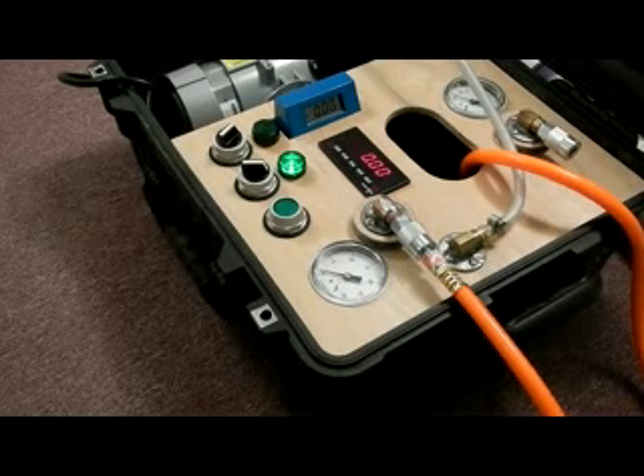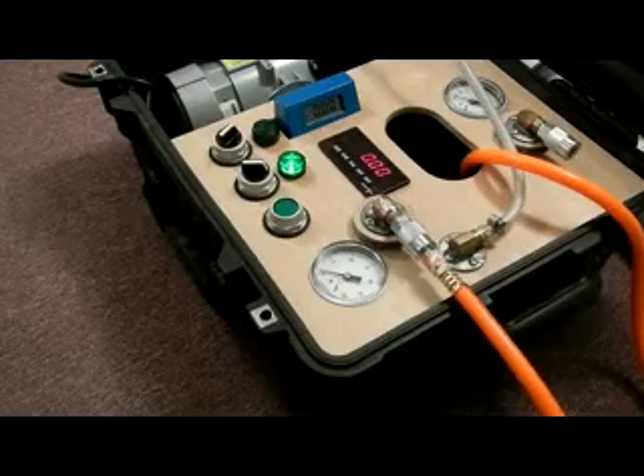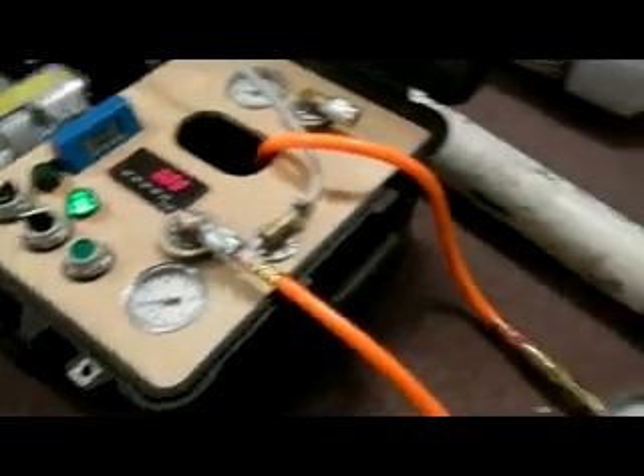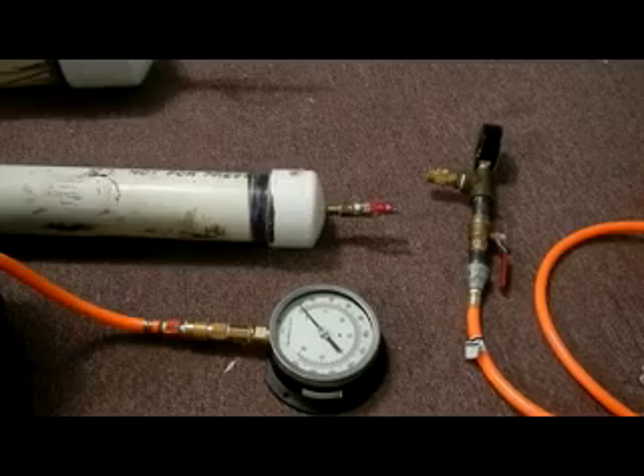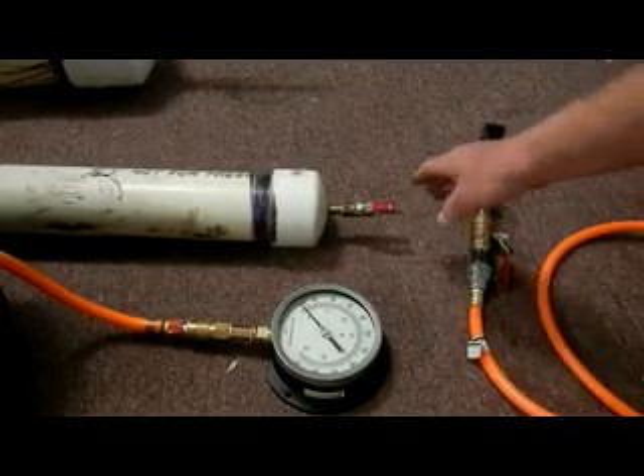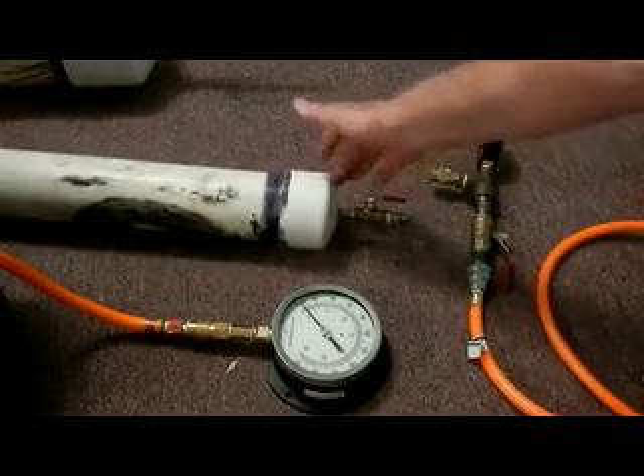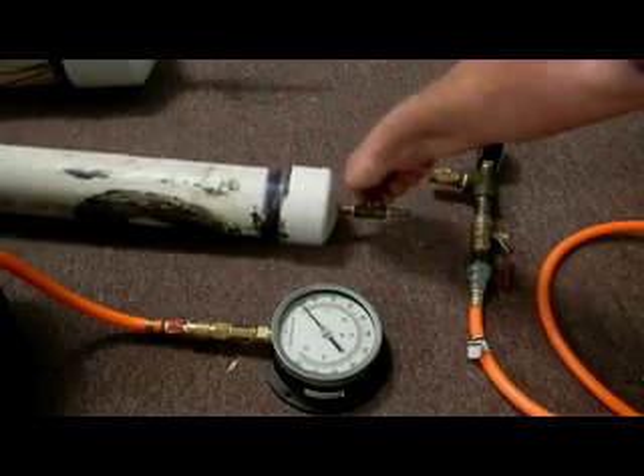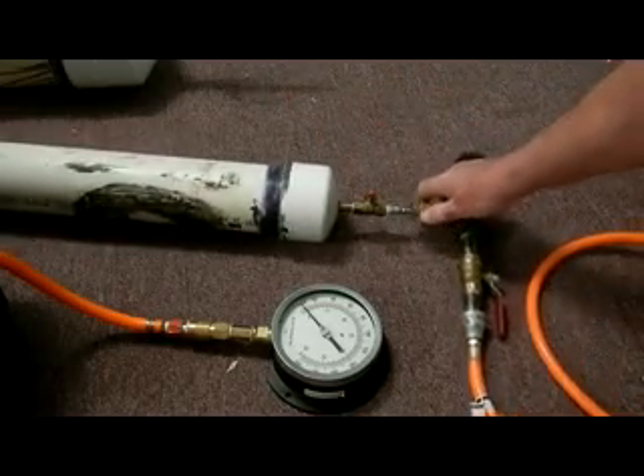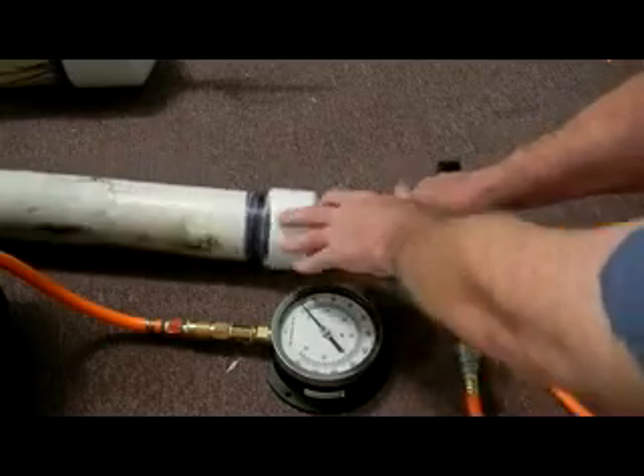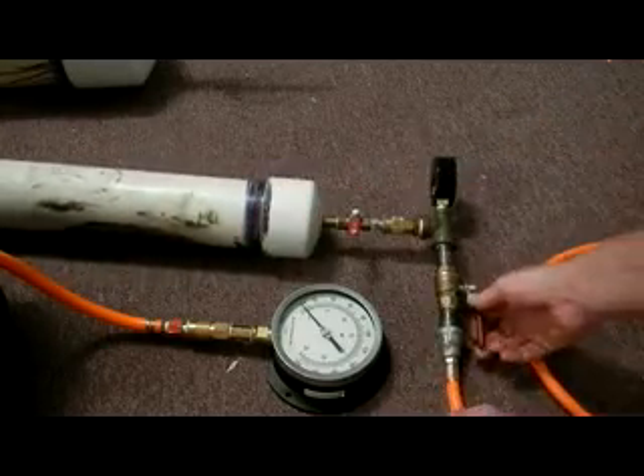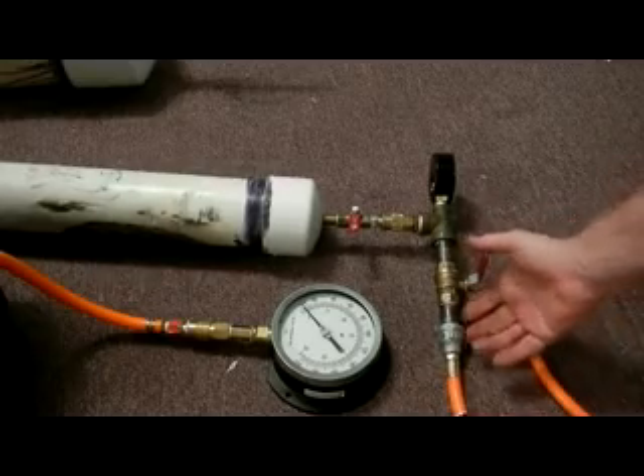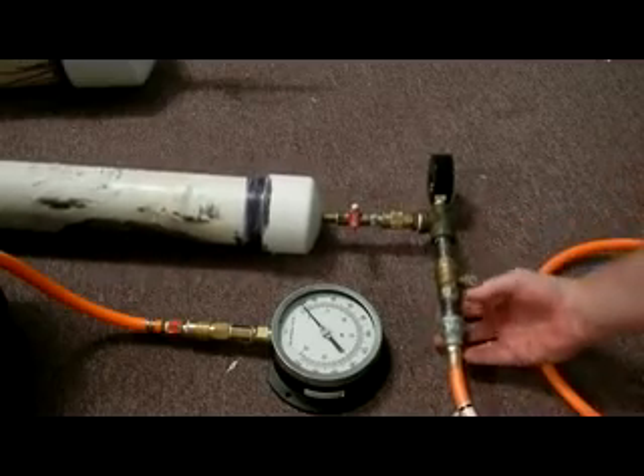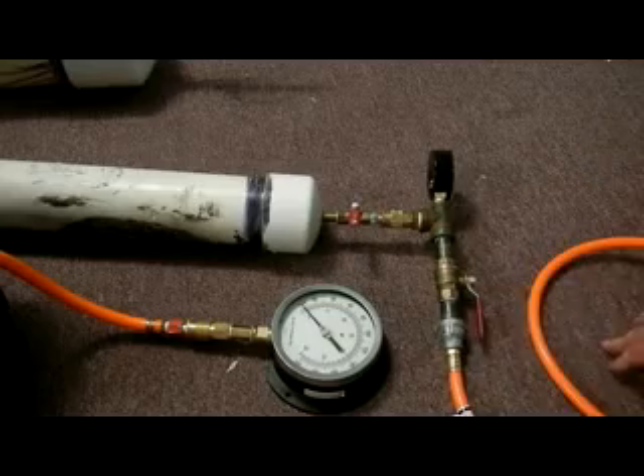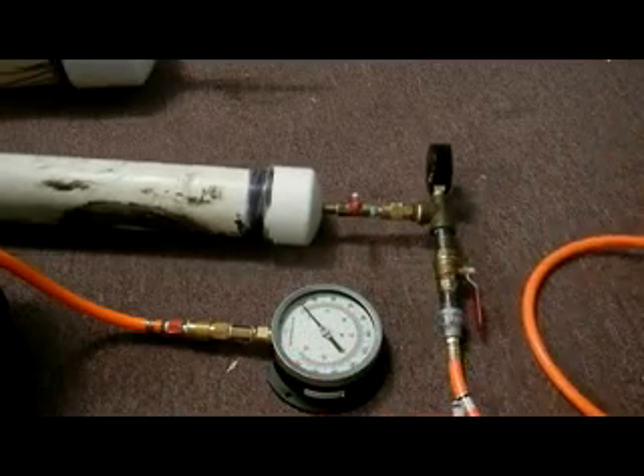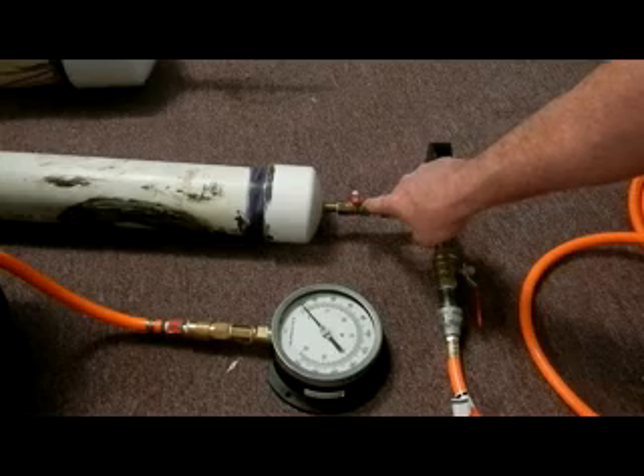We're now going to hook up our test cylinder and our manifold. This is the test cylinder, which would be your void, your close-off valve. We're going to hook up the manifold. We can close this valve, but at this point it doesn't matter, we can leave it open. We're going to turn on the compressor and pressurize just the hose and the manifold up to this point.